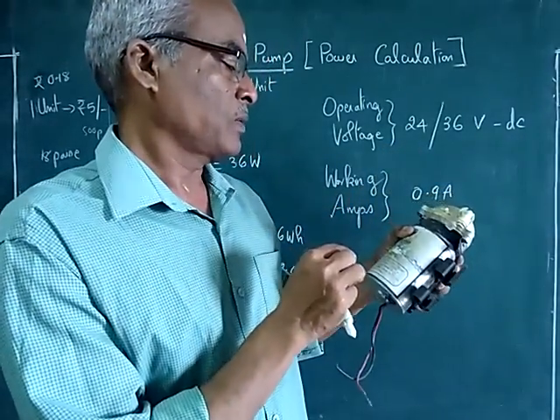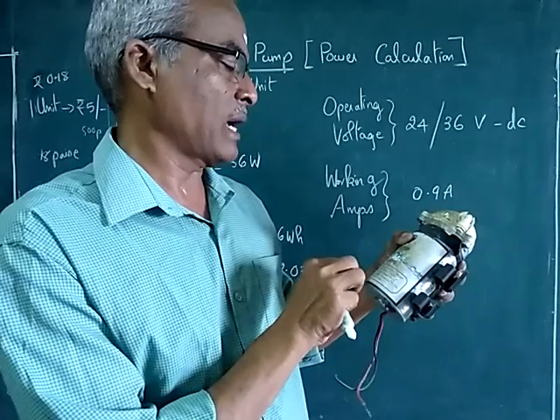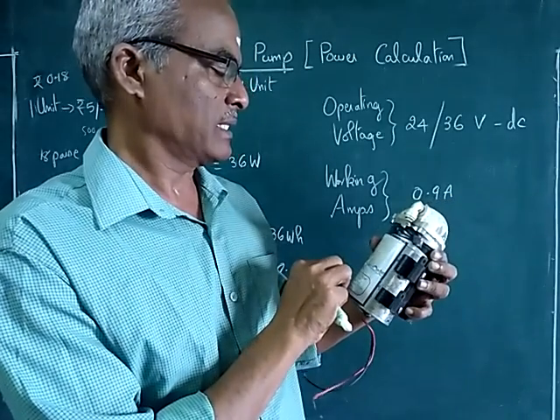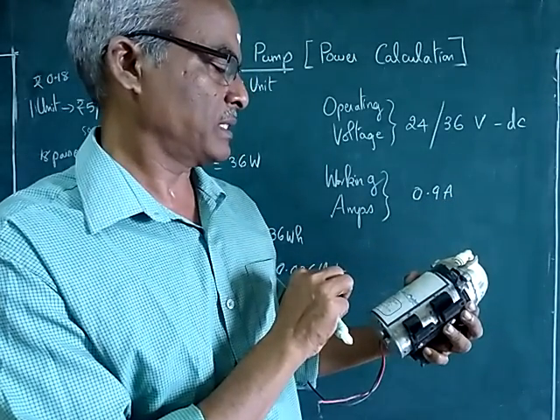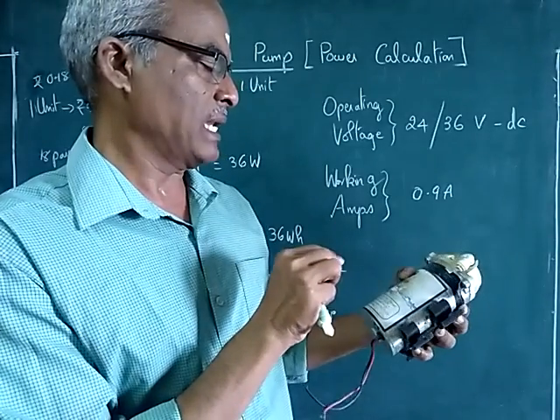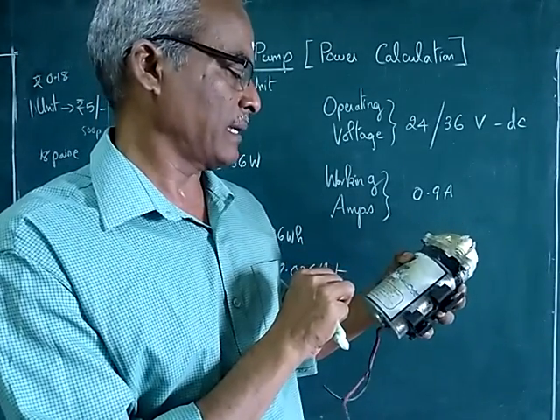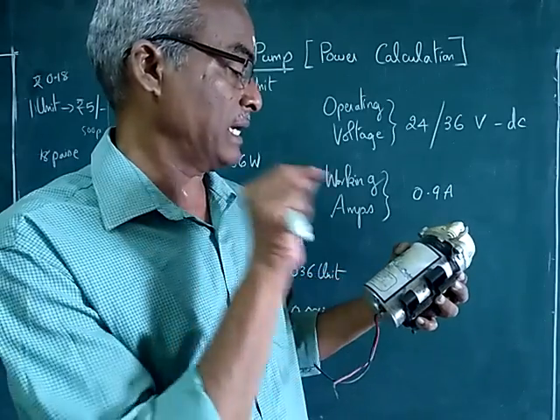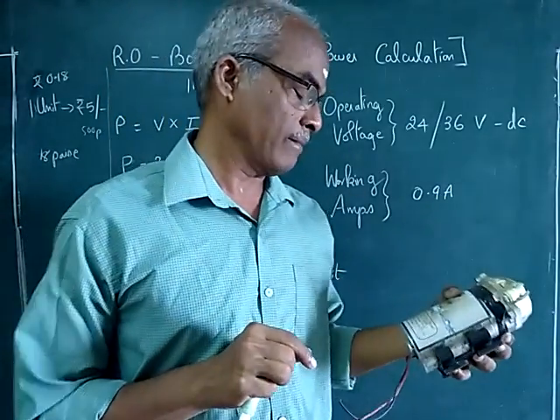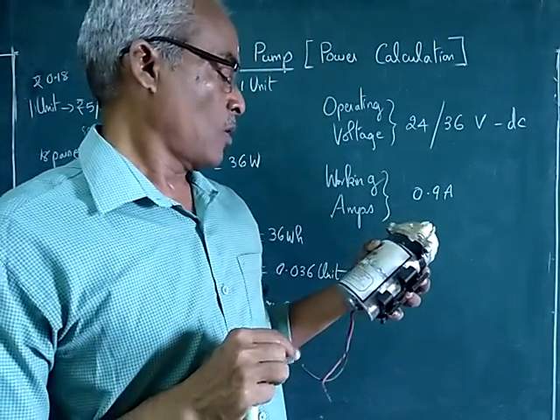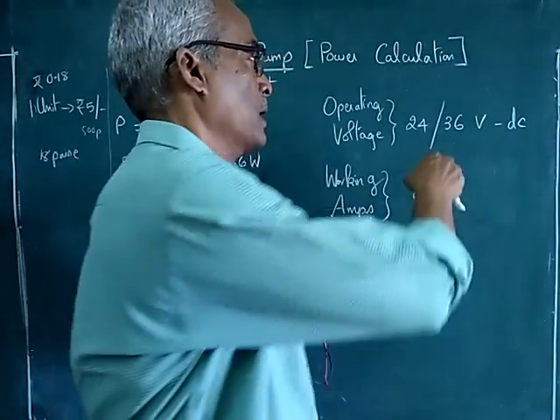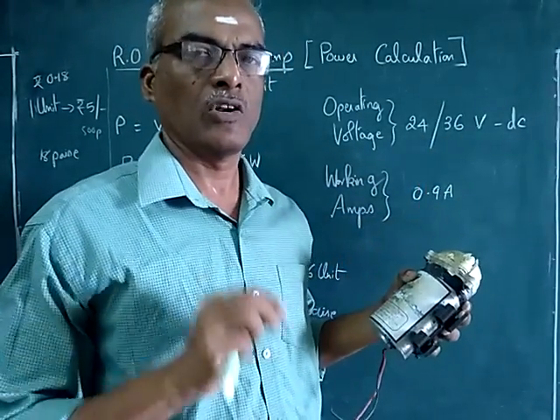What are the important details we have from this? Nominal flow rate is 1.6 LPM, pump pressure 130 psi, maximum inlet pressure 60 psi, operating voltage 24 or 36 volts DC. It is not AC, it is DC—24 volts or 36 volts.